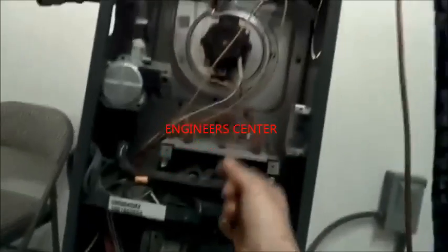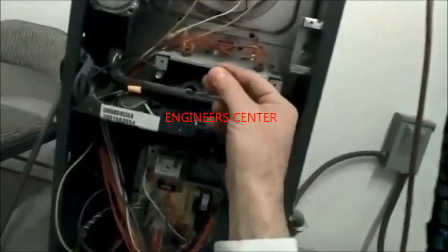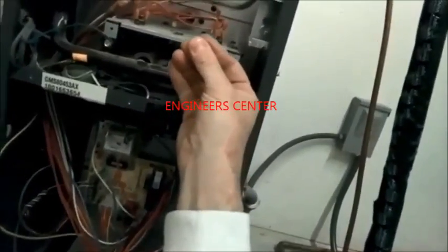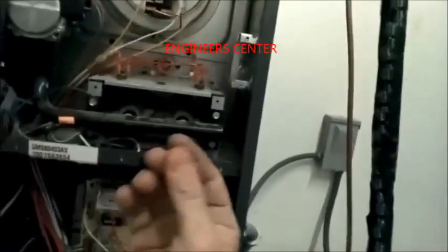And so next thing in our sequence of operation is going to be the glow igniter is going to start glowing, or the sparker might spark. If it's a glow ignition, the glow ignition is going to glow. It's going to get bright red, and just when you think it's starting to go out, the gas is going to open. It's timed just right. Boom, gas ignites. It should ignite immediately. And then this flame sensor here is going to sense that heat from the flame and turn it into millivolts, sending it back down this wire to our board, telling it the flame is lit, we have ignition, and so it's okay to continue letting out gas and continue heating. Then this one is wired where the blower motor will come on maybe 60 seconds later. After it gives a chance to warm the heat exchanger up, the blower motor should come on off the board, the fan relay.